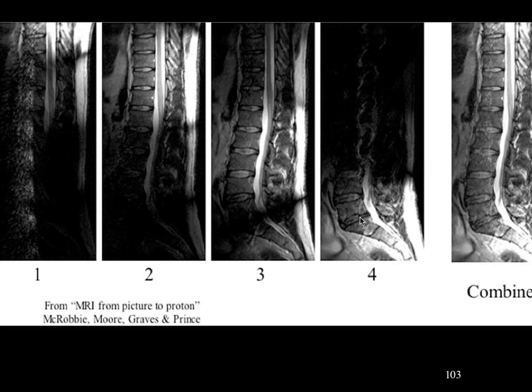Phased array coils can be four or more separate coils — some people use 8, some use 16-coil arrays, and some scanners are equipped for 64, though I don't know of any coils that go up to 64 right now. This is phased array imaging, used all the time now to get higher signal-to-noise per unit time. What I want to talk about now is not so much getting higher signal-to-noise, but how we can use this to do faster imaging.